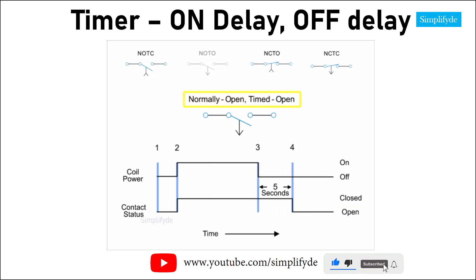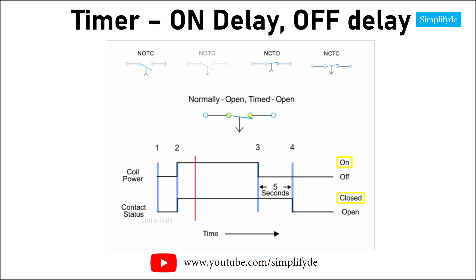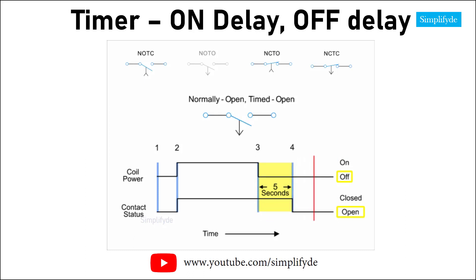Next, we have the normally open timed open (NOTO) contact. Similar to the NOTC contact, this type of contact is normally open when the coil is unpowered or de-energized, and closed by the application of power to the relay coil. However, unlike the NOTC contact, the timing action occurs after the coil is de-energized. Thus, the contacts close immediately when the coil is energized, and open five seconds after the coil is de-energized.